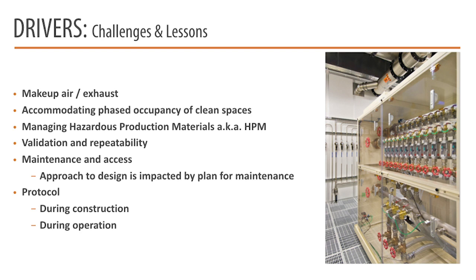The makeup and exhaust balance is key, touched on that. Accommodating phased occupancy - this one's huge. We often think of what's the overall load, what tonnage of cooling I need, how much air do I need to push out of a makeup unit. Well, you're thinking of when the suite is fully built out - but what if it's done in four phases and you're going to operate at 25% fit-out for a year? Can you turn down your air handling equipment and chiller plant to that low end? That can be the gotcha, often more so than the high end. Understanding how something's going to be phased, the timeline, and whether you can hit that low end with your systems and equipment.